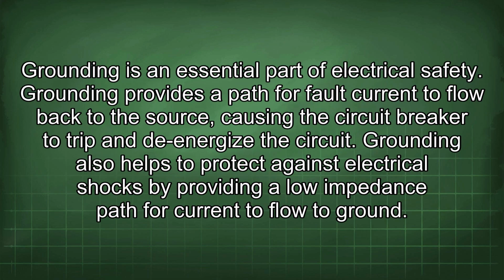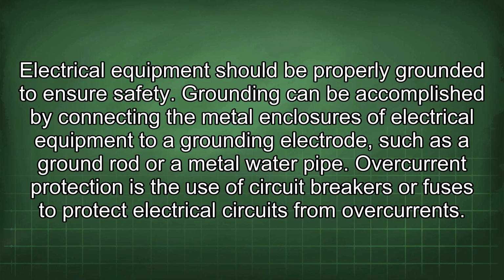Grounding is an essential part of electrical safety. Grounding provides a path for fault current to flow back to the source, causing the circuit breaker to trip and de-energize the circuit. Grounding also helps to protect against electrical shocks by providing a low impedance path for current to flow to ground. Electrical equipment should be properly grounded to ensure safety. Grounding can be accomplished by connecting the metal enclosures of the electrical equipment to a grounding electrode, such as a ground rod or a metal water pipe.